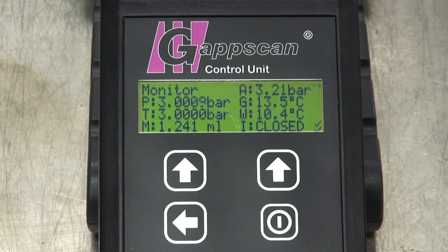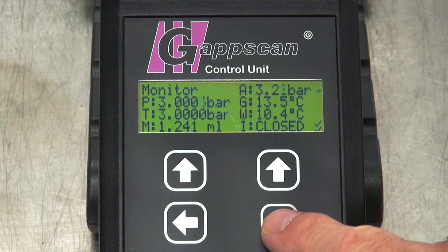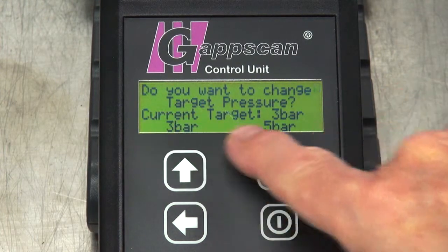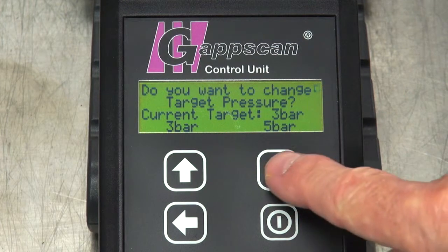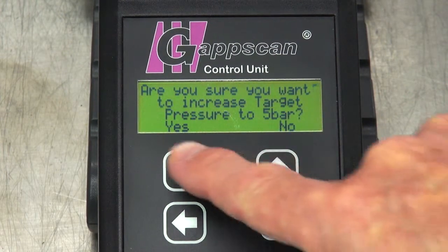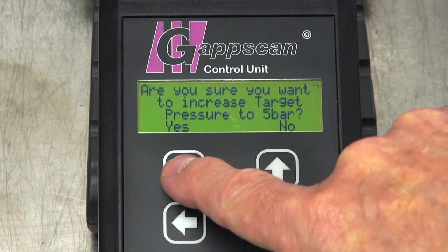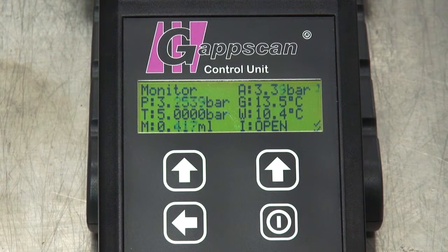Depending on the condition of the exchanger, you may want to run the test at a higher pressure. At a higher pressure, the crack will open up more and therefore be easier to detect. If there are no external leaks, you would want to do the test at the highest pressure possible. From monitor mode, press the I/O key. You will be asked if you want to change the target pressure. Select 5 bar and then confirm. You will see the live pressure P increasing.